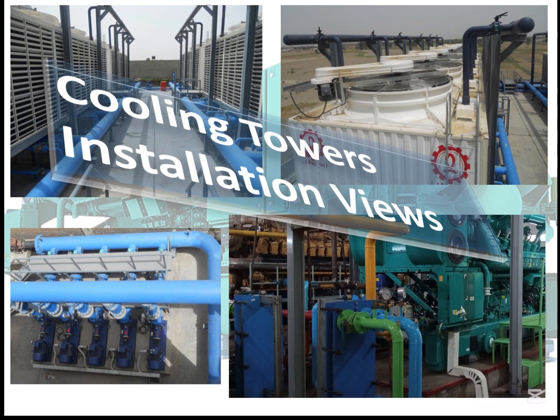So from here, where your air cooling tower is, the circulation water pump can bring the fresh water and hot water from you. The heat exchanger is always installed close to the engine, one for the LT circuit and one for the HT circuit. So this is just an overview of the cooling tower installation. And with this, our coolant circuit is complete. So we have one circuit, HT, that is high tension and high temperature. The other is the LT, low temperature circuit.